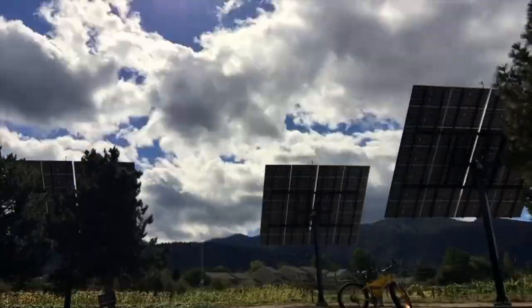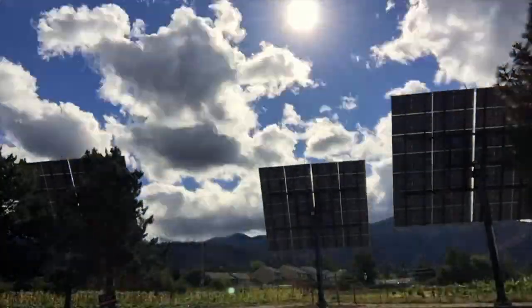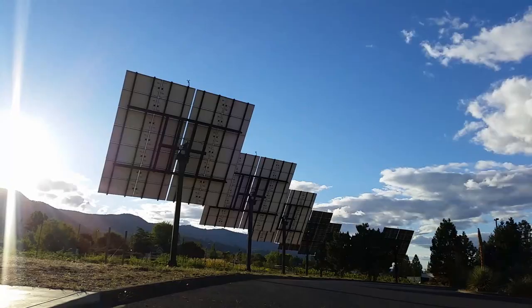The model S1 utilizes an all-electric control and slew drive actuator system that keeps the PV array pointed directly at the sun all day, every day of the year. The heart of the tracking system is our proprietary drive core, which includes slew drive actuators, electric motors, and an advanced control system. It mounts right on top of the pole with a compact steel assembly. The control system incorporates a sophisticated proprietary GPS-based algorithm. We don't use any hydraulics or linear actuators — just exceptionally high-strength actuators and electric motors. Our trackers carry the UL3703 listing and are load tested for wind ratings of 120 miles per hour.